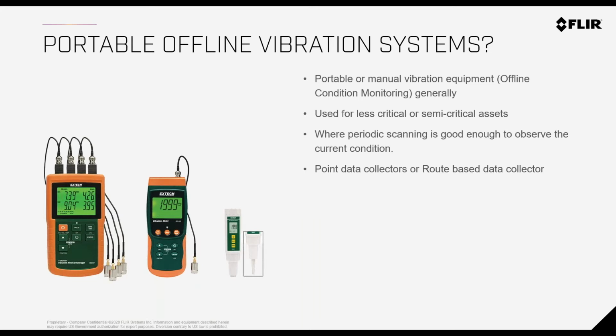So from FLIR and Extech, if you didn't know, Extech is a brand of FLIR. FLIR acquired Extech about 12, 13 years ago. So Extech actually has some portable vibration solutions. These are going to be used for more like one-off testing. Maybe it's not something that you test every day, or maybe it's more like once a month you want to test it. You can track your results and then compare it to the month prior and the month prior to that. So these are contact portable vibration meters.